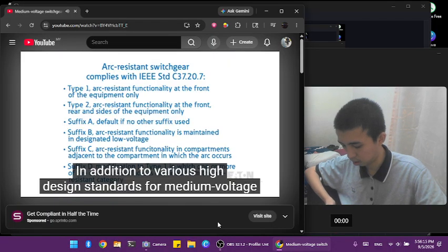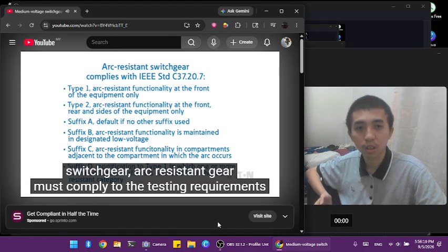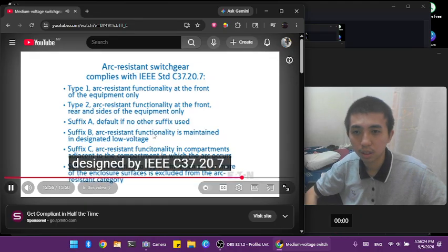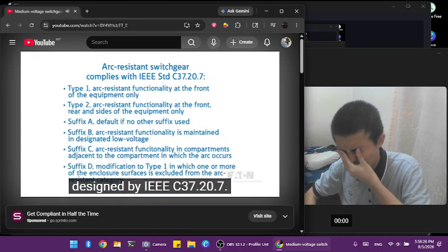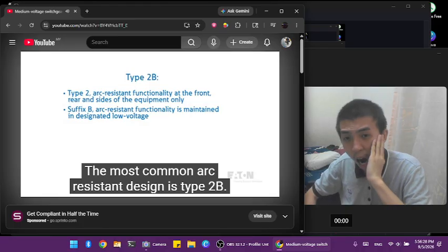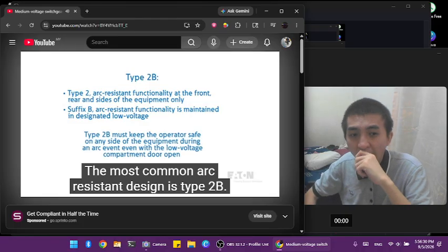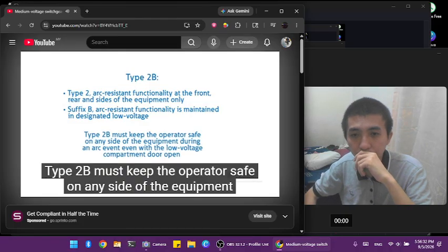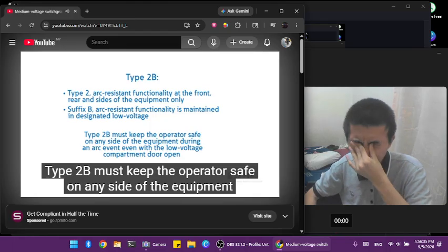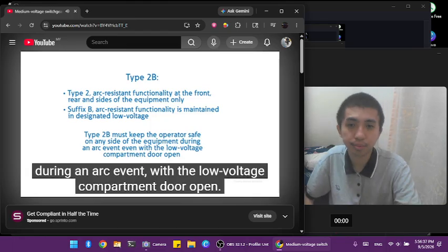In addition to various IEEE design standards for medium voltage switchgear, arc-resistant gear must comply to the testing requirements designed by IEEE C37.20.7. The most common arc-resistant design is Type 2B. Type 2B must keep the operator safe on any side of the equipment during an arc event with the low voltage compartment door open.